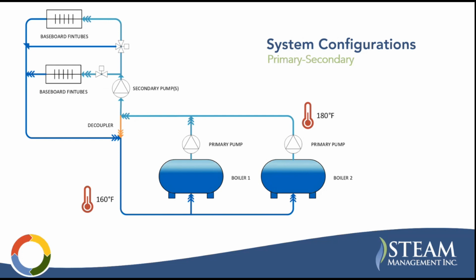Alternatively, you can have a primary secondary system. And the idea here is you have this primary loop that circulates. In the past, this has often been a constant loop. So you have a constant flow through this, and then you pull off of this with your secondary pumps to pump out to your users. And so you have a secondary loop.